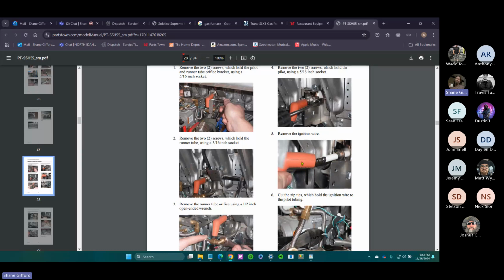But this guy right here, this whole entire thing is insulated because you've got lots of open metal, and then you've got electricity. Well, electricity likes to arc, so be careful when this is lighting. I usually don't like to hold on to the unit or touch the unit or ground myself to it while it's sparking, just in case it arcs to the case and I just lit myself up. But this piece right here, you do want to make sure it goes all the way back and it should snap in. I have not seen one in proper working order that did not actually snap in, or you can feel it engage.